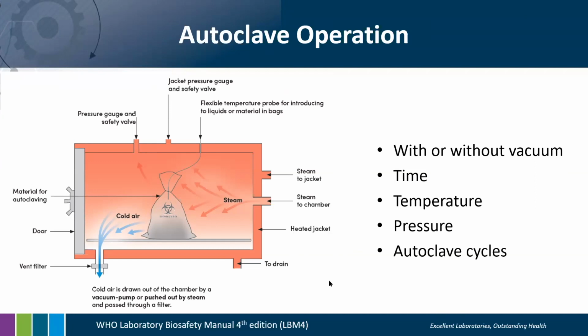There are autoclave cycles operating with a vacuum, which is called an active type of autoclave, or without vacuum, which is called a passive autoclaving process. With the active type, we are talking about autoclaves that have a vacuum pump, and the chamber, which is what you see inside this figure, is subjected to successive pressure changes to draw air from the chamber through a vent filter.